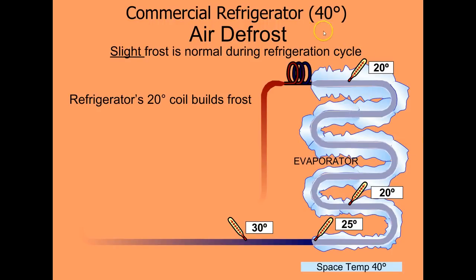We have a commercial refrigerator that is running a box temperature of 40 degrees Fahrenheit. It's using an off-cycle or air defrost to get the frost off the coil. There will be slight frost on the coil during the refrigeration process because the coil temperature is 20 degrees Fahrenheit, and that's what you need to have to get the box temperature down to 40 degrees Fahrenheit.